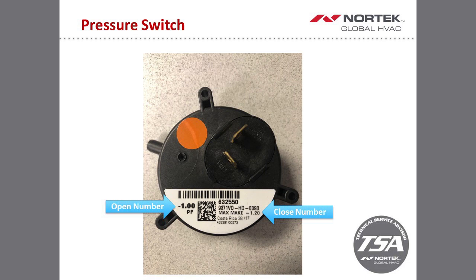What we have here is a picture of a standard pressure switch. What I've highlighted here, the bold number, is the opening pressure. That's what you're probably most familiar with on the actual pressure switch. I've also highlighted the close pressure. The text is a little bit smaller and not bolded. That's the vac reading it takes in order to close that pressure switch. For our example, it works out to an even 20% in order to close this particular pressure switch. But that is a general rule of thumb you can use in the field when troubleshooting.